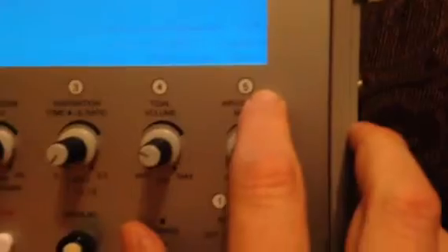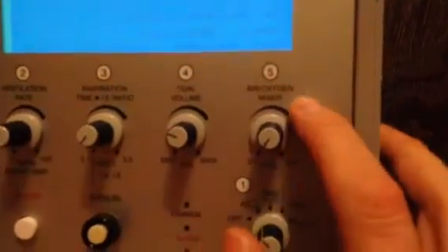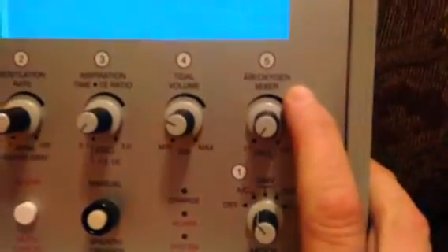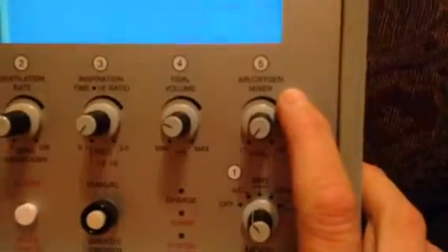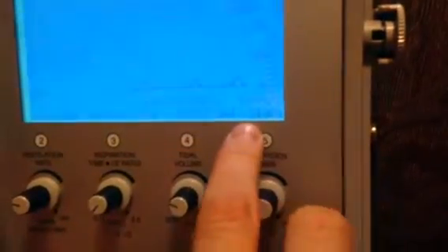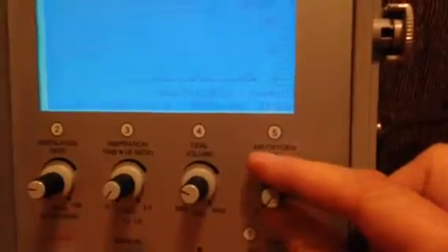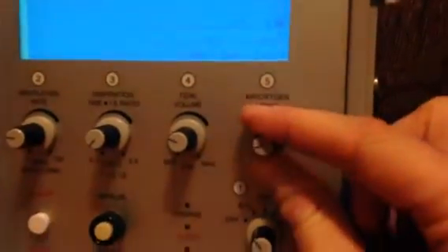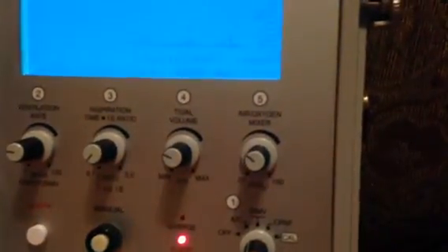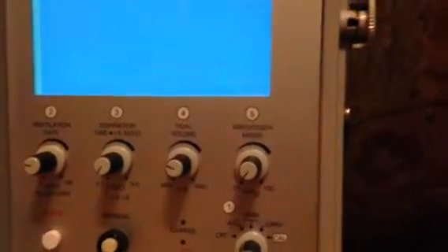One of the final steps is step 5, and that's our FiO2, or percentage oxygen, that the patient's going to get. Right now we're using room air, and we're using the internal compressor on the ventilator, so it's telling me it's delivering 21%. You'll notice if I try to increase the FiO2, the ventilator alarms. So let's reset that alarm and dial it back to 21%.